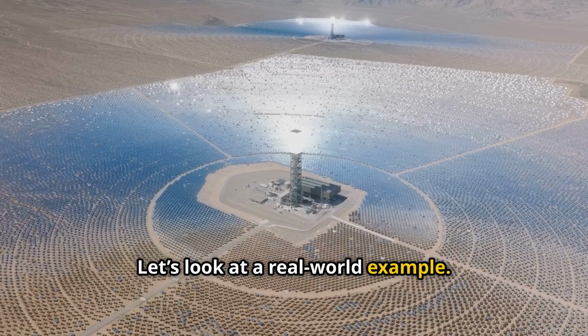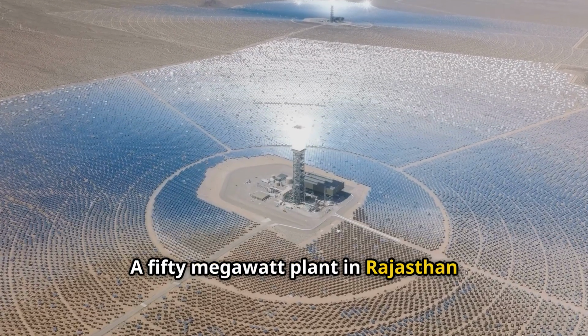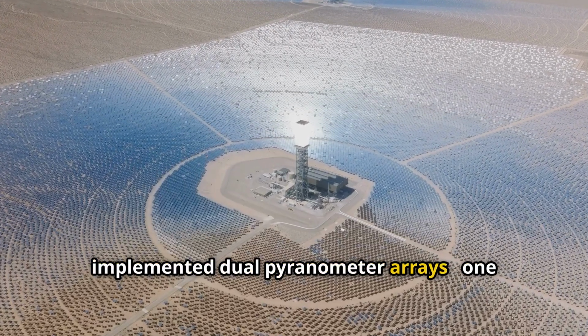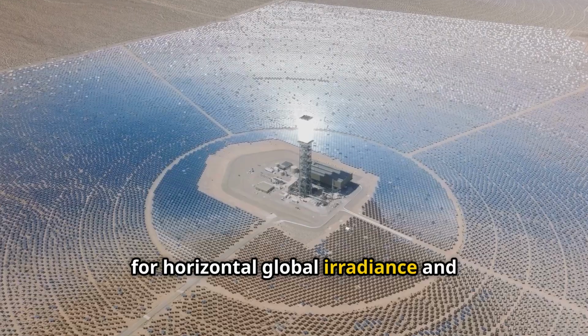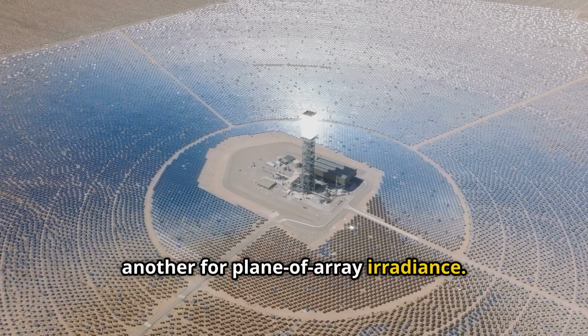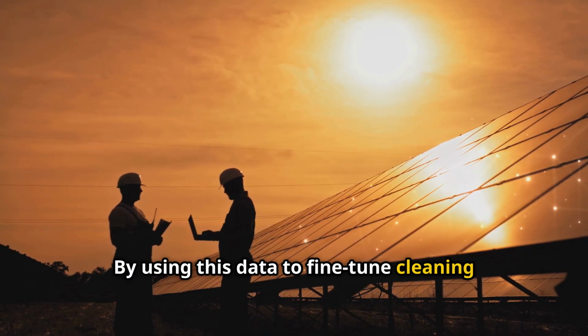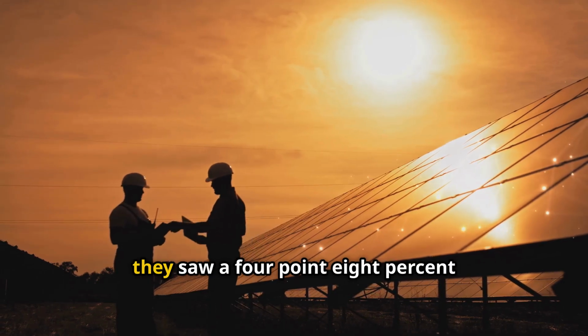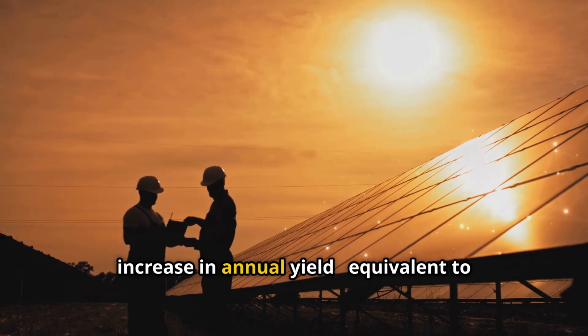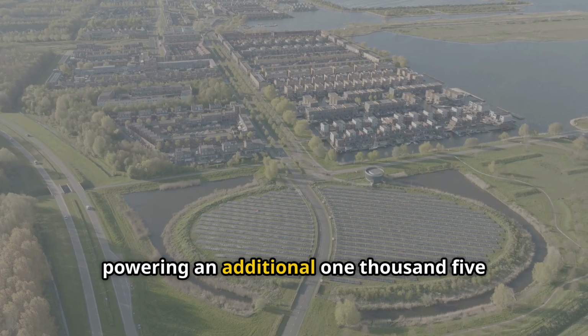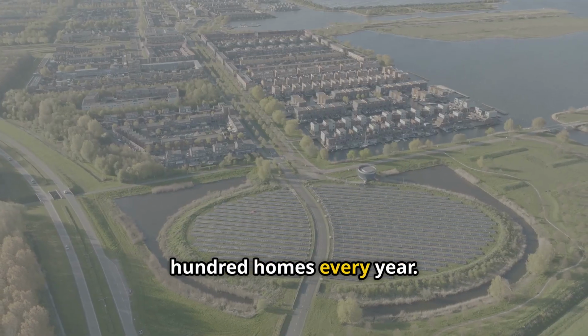Let's look at a real-world example. A 50-megawatt plant in Rajasthan implemented dual pyranometer arrays, one for horizontal global irradiance and another for plane-of-array irradiance. By using this data to fine-tune cleaning schedules and tracker positions, they saw a 4.8% increase in annual yield, equivalent to powering an additional 1,500 homes every year.